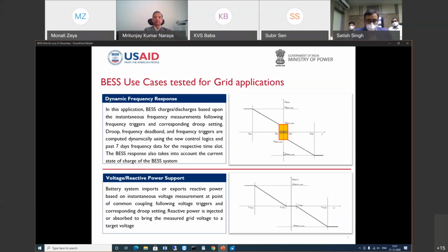So when we talk of frequency regulation services, there is a dead band. For example, if we set 49.95 and 50.05 as a dead band, batteries would not act within this dead band. However, when frequency goes below 49.95, that means there is a generation deficit in the system. Your load is more than generation. In that case, the battery acts as a generator and provides the necessary power to the grid, so that your frequency becomes within the pre-specified band. And vice versa, if frequency is high, the battery will act as a load.